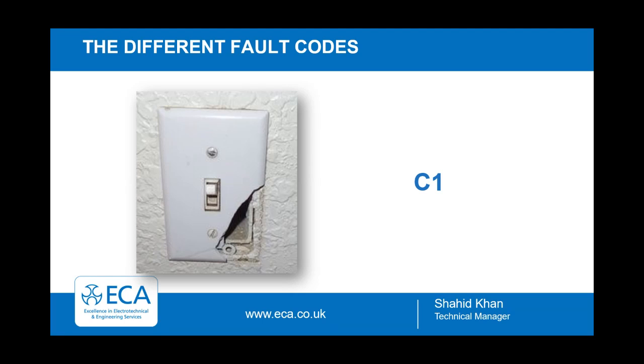C1. Yeah, that's it exactly. It's a failure of basic protection. You can basically stick your finger in and you could touch a live part that's supposed to be live. In terms of regulation number, it contravenes 416.2.1, which is the one that talks about the IP requirements on the various surfaces of barriers or enclosures.